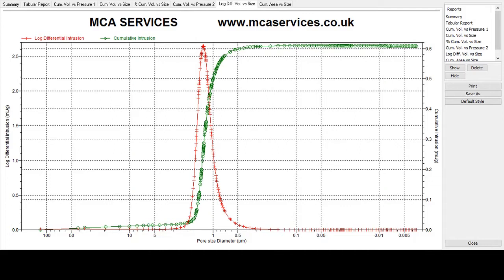We'll show the various stages involved in the analysis and we will be showing some of this on the instrument software. But the first step is to load the penetrometer into the AutoPore.